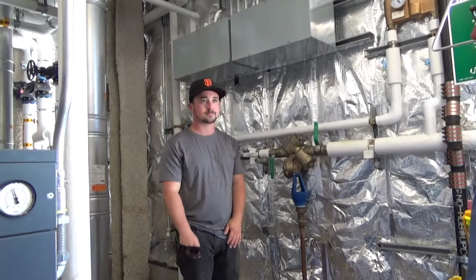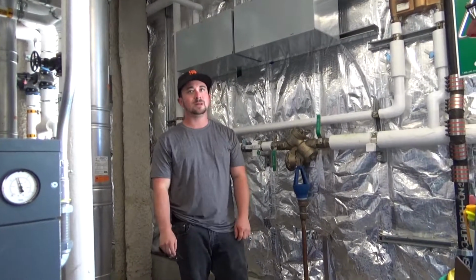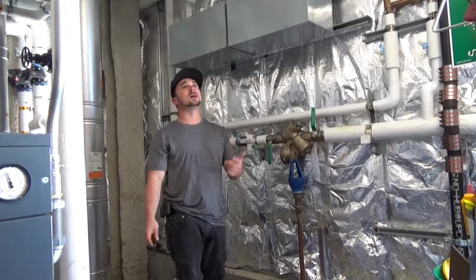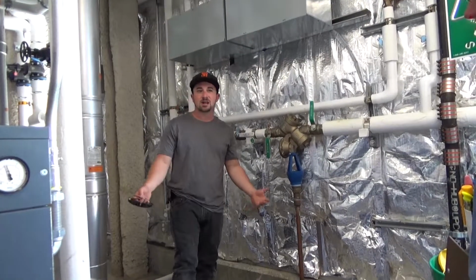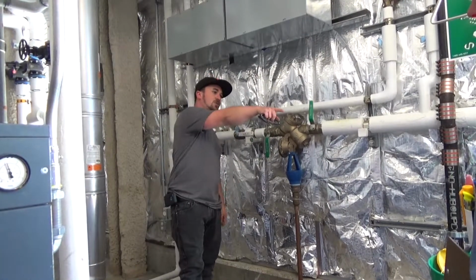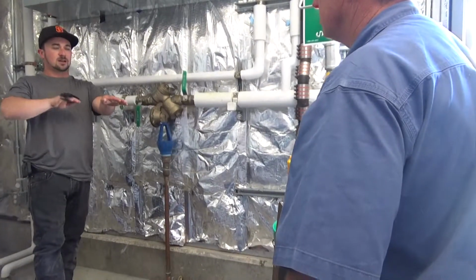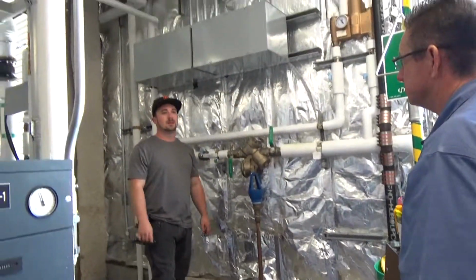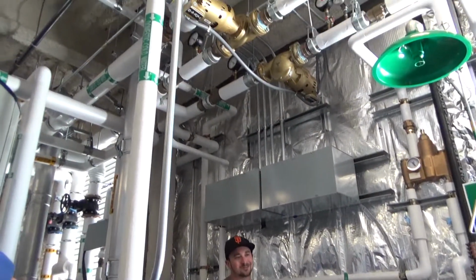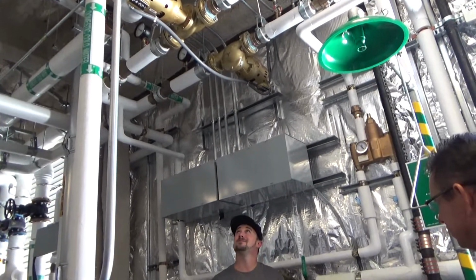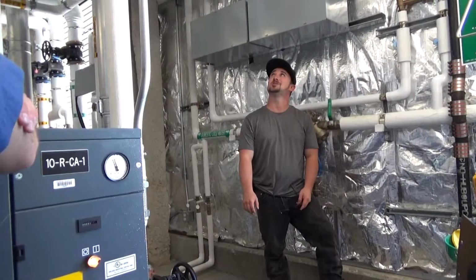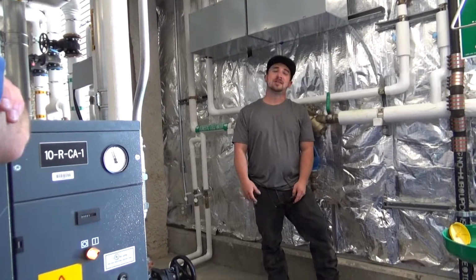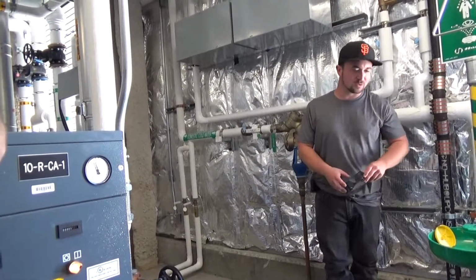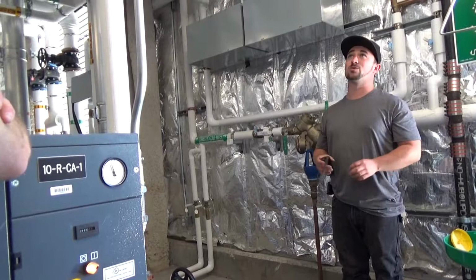What's the general life expectancy of these couplings? The couplings? Well, with these, since there's no alignment, they're usually pretty good. They can't go out of alignment. Like with those 1510s, eventually they'll work themselves out of alignment, and then it'll start tearing up those inserts. With these, they're locked in, so they'll last a good amount of time. I can't really give you an amount of time, but I'd say 10 years. These are pretty simple pumps. You guys hopefully will never have to touch them until you have to replace them.